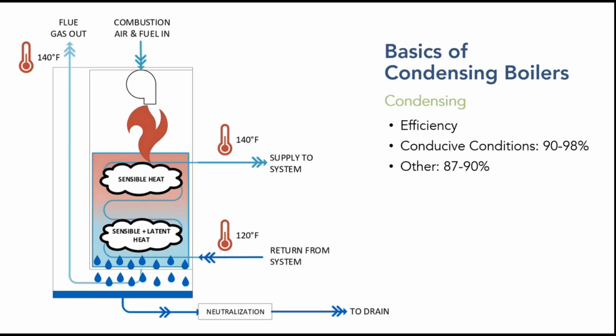So this is the condensing boiler concept. We're taking combustion air and fuel in, going across the coil, and you're getting that initial sensible heat similar to the conventional boiler, but you have some excess surface area here, which is taking that flue gas temperature down further to the point at which the water in the flue gas starts condensing and dropping out of the flue gas, and you're getting that additional latent heat as well. And you can get really low flue gas outlet temperatures here.